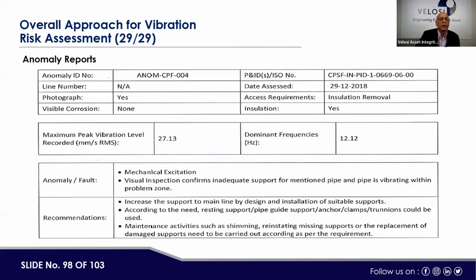And here, the recommendation has been given in the anomaly report. For example, if you see the anomaly number, then the P&ID number, date assessed, and maximum peak vibration level is 27.13, and dominant frequency was 12.12. Mechanical excitation: visual inspection confirmed inadequate support for the mentioned pipe, and the piping is vibrating within the problem zone.